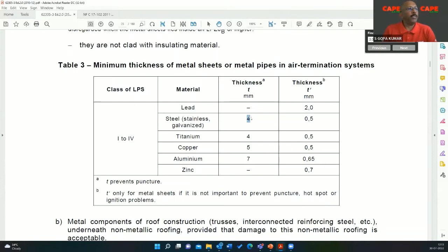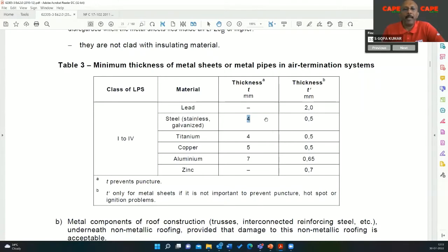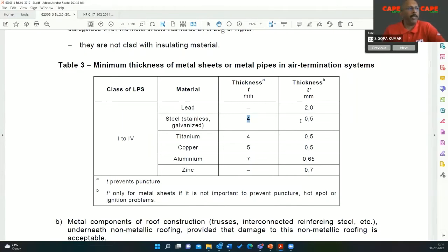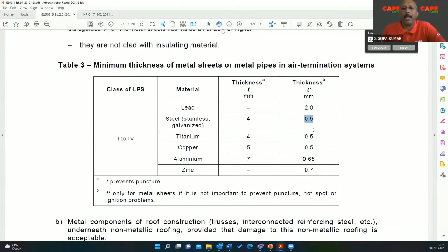If the thickness is between 0.5 and 4 millimeters — in India we don't even use 0.5, our sheets are even thinner — lightning may create a puncture on the sheet, which could ignite a fire or cause accidents. If you want to avoid a puncture in this case, you have to use an air termination system: make a mesh and connect it to the sheet itself, avoiding a direct lightning hit onto the sheet. If the thickness is less than 0.5 mm, it is dangerous to use the sheet as air terminal.